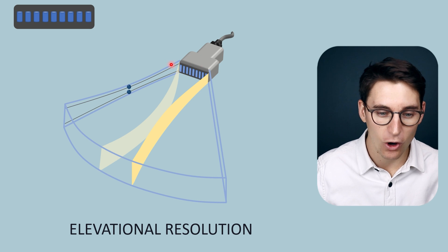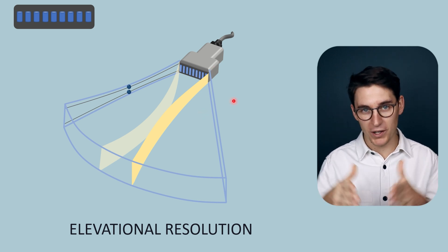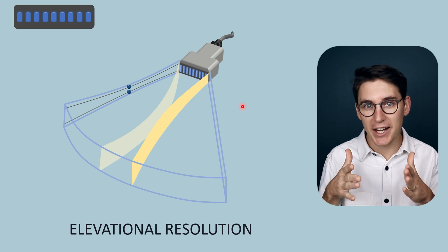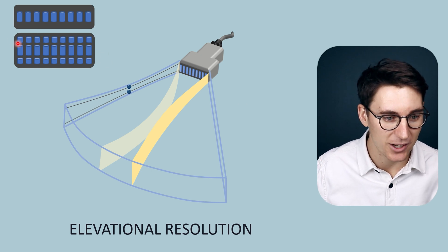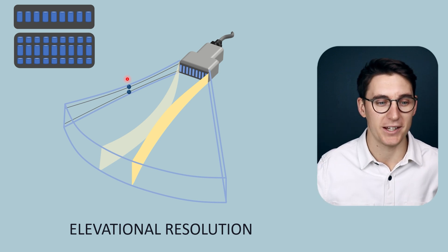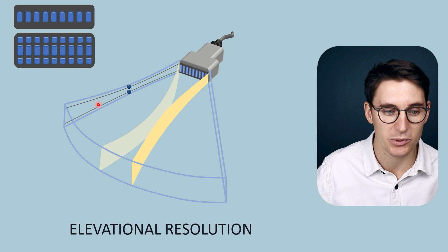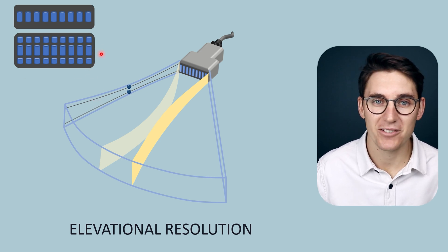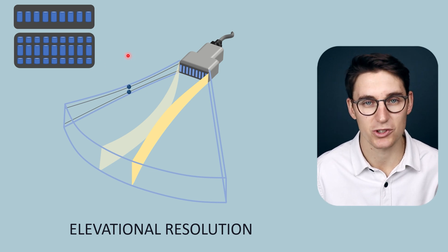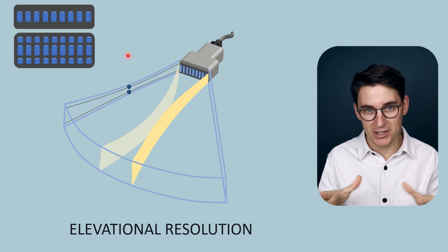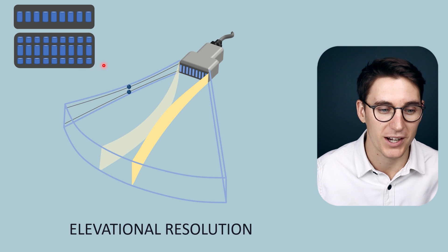We can place an acoustic lens over the front of the transducer to focus the beam height down to a set focal depth, much like an acoustic lens focuses beam width. We've seen that phased arrays can change focal depth in the lateral plane; the same applies to elevational resolution. Adding more transducer elements in the elevational plane creates a 1.5D transducer array. A 2D array has equal rows and columns; a 1.5D array has fewer rows than columns, typically 5 to 7 rows. These elements can be phased in the elevational plane to achieve the required elevational focal depth.